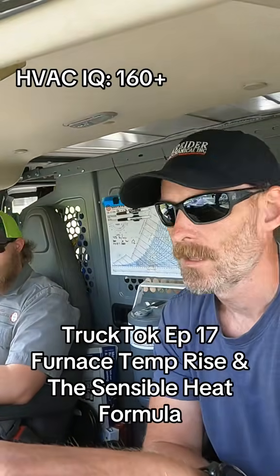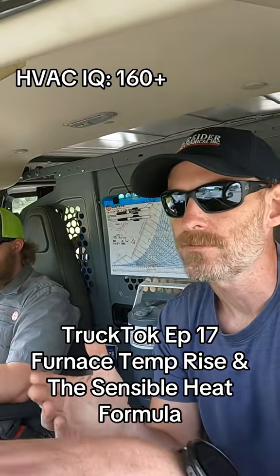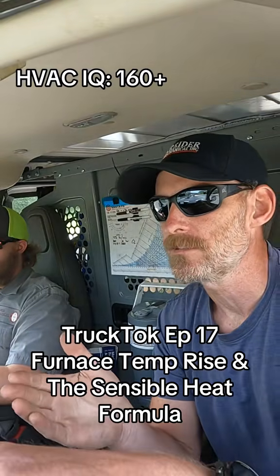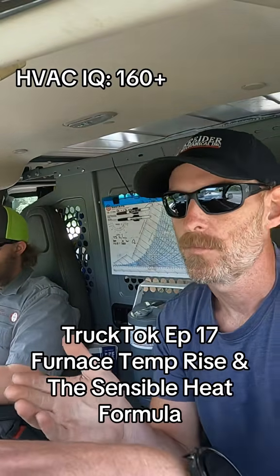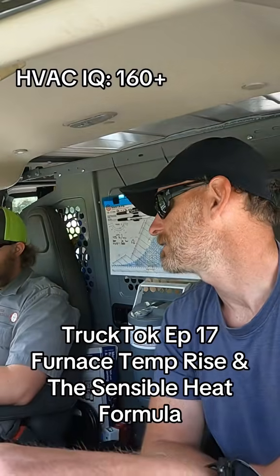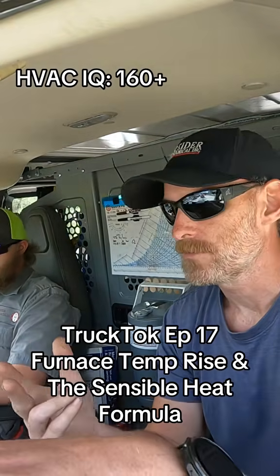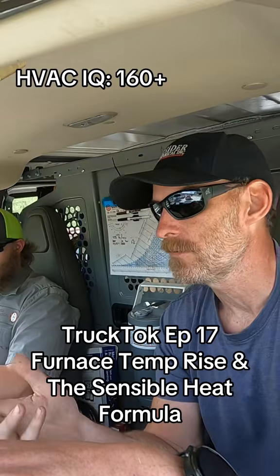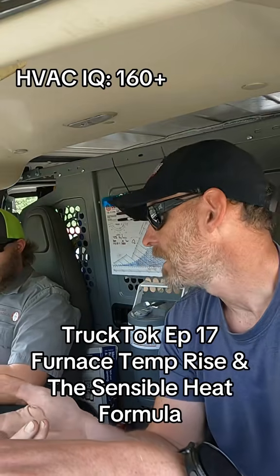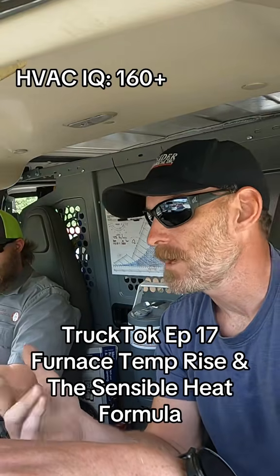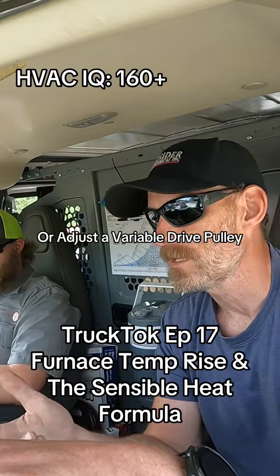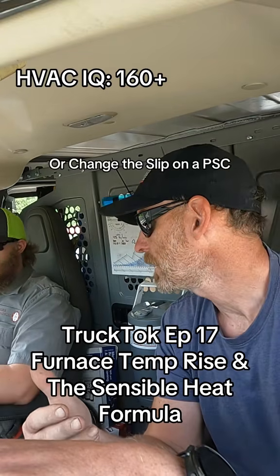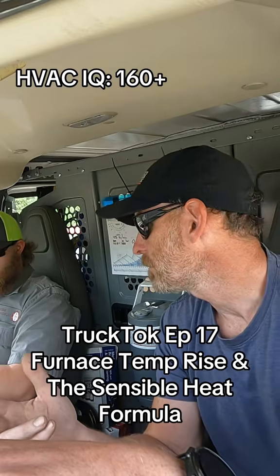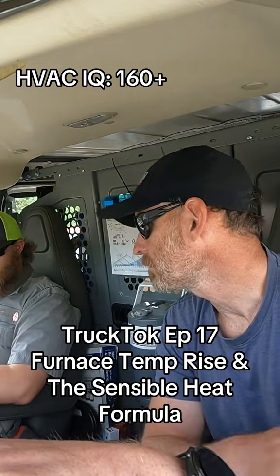right? Yes. Well, see, the manufacturers know that HVAC dudes don't exactly all carry around precision airflow measuring devices. But what we do have are temperature probes. So if you can put one in a return and a supply and calculate the temp rise, you can manipulate an electronically commutated motor for its speed in order to get that temp rise right. You know what I'm saying? You might mess up some other stuff in the process depending on who installed the ductwork and whether they did it right.